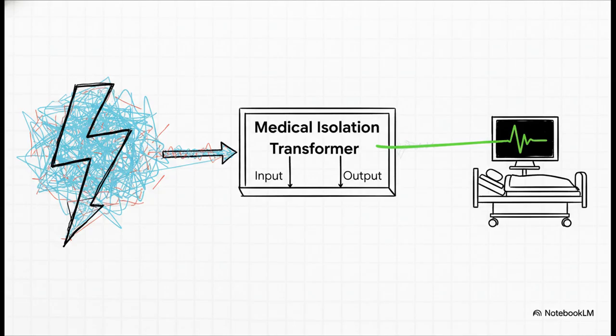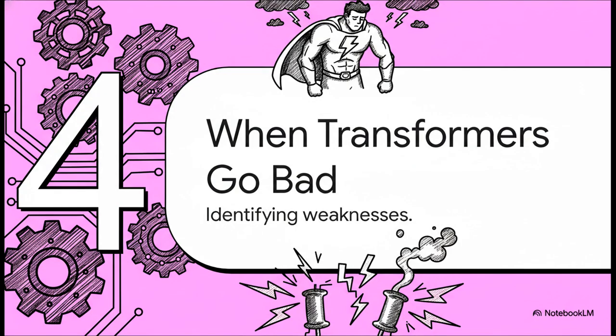In places like an operating room, even the tiniest stray current from the grid could be fatal to a patient. So what these transformers do is create a complete electrical bubble. It's called galvanic isolation between the grid and the medical device. This makes absolutely sure that no stray current can ever reach the patient. They are, quite literally, lifesavers. So, transformers are efficient, they're versatile, and they even save lives. But they aren't invincible. And that leads us to our next section, when good transformers go bad.